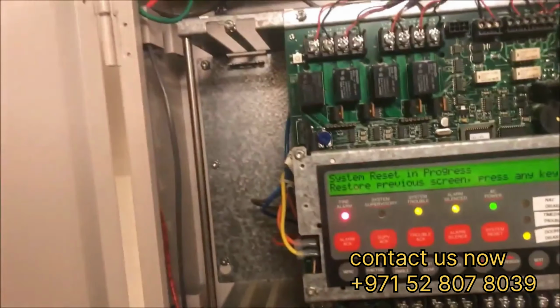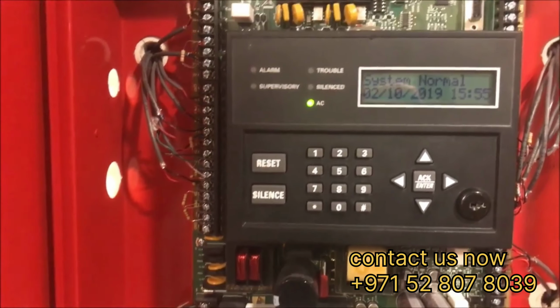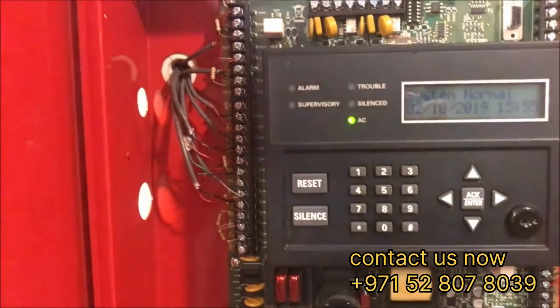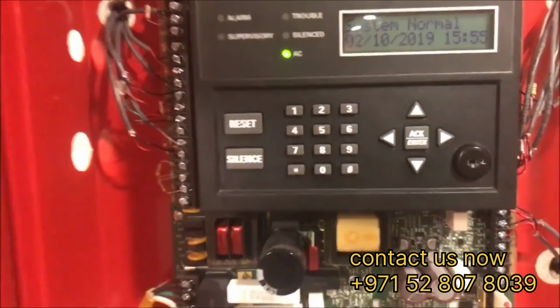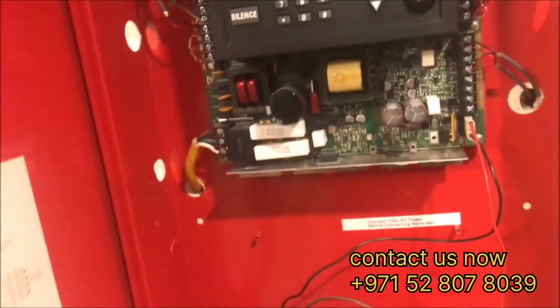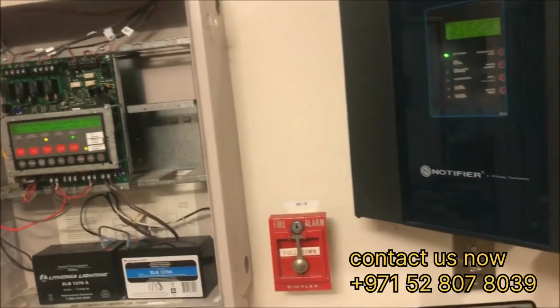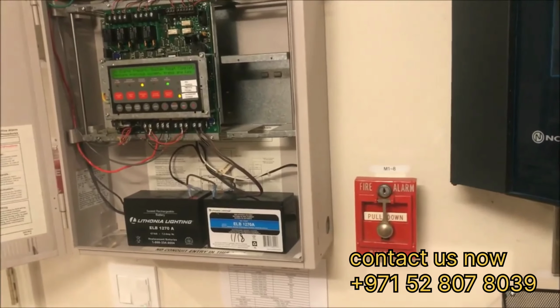The same thing works with intelligent heat detectors. So this one has a heat detector built in. You can see the real-time temperature that the heat probe is at. With a conventional panel, you can't do any of that. You just know either it's an alarm or it's not. So there are drawbacks to both. These ones are cheaper and usually good for smaller things, and they work with more devices and a wider range of inputs. These are better for large scale, they're more expensive, and only work within their brand, but you get more precise monitoring.